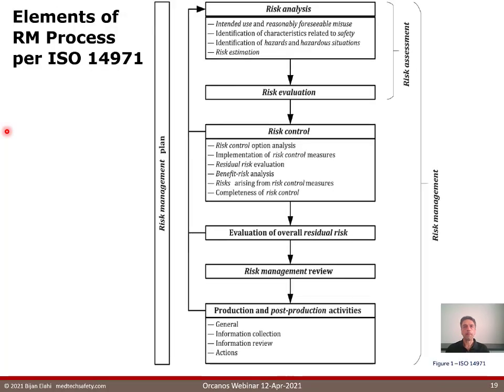In this slide, I am showing you figure 1 of ISO 14971. It shows the framework for risk management. As you can see, it has some major sections. The top section is risk analysis, and it stipulates certain activities, for example, identifying the intended use and reasonably foreseeable misuse, identifying the characteristics related to safety, identifying the hazards and hazardous situation, and estimating risks. This is the risk analysis section. Now, by the end of this section, we know what the estimated risks are, and then we can evaluate those risks. And then the next section is risk controls.